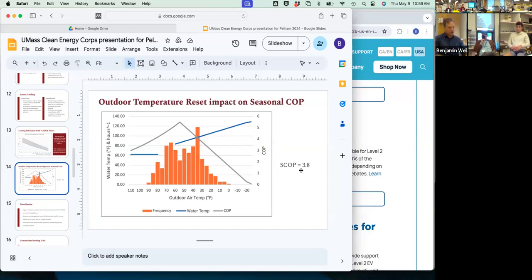One difference, depending on how we control these things, because we didn't really work into the details of the unit ventilator, the future unit ventilator controls, partly because Rupert's, like, I feel like you've got that. And one way to approach that would be if there's no call from the thermostat, the fan can actually shut off because there's no ventilation required. It's already being met by the roof. Yeah, so when your ventilation is taken care of and the thermostat's satisfied, valve closes, the fan turns off, everything gets really quiet. It would be like a residential unit, basically, on demand.